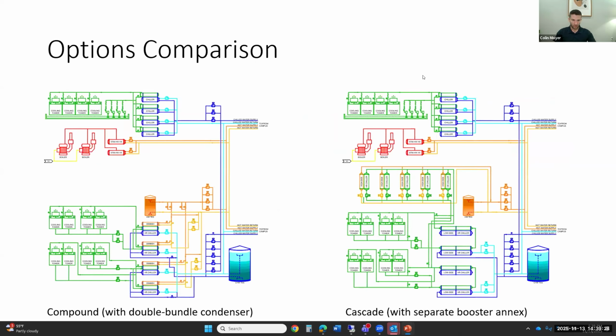So put those two different options together on this diagram. The compound arrangement or the multi-stage arrangement on the left, shown as if we could get a double bundle condenser. Alternatively, if the manufacturers aren't offering that, you've got to have a hot water to tower water heat rejection system, which is an additional cost. Versus on the other side, a representation of a cascade arrangement at the TES plant.